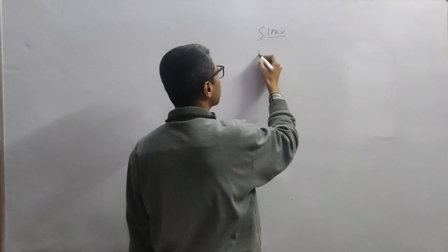This time the machine synchronizes 14 breaths of the patient into mandatory ventilation and lets the patient take 2 extra breaths. So 2 will be the extra breaths of the patient and the machine will give 14 mandatory breaths. But if it was not synchronized, it would give a total of 14 plus 16 equal to 30 breaths. So that is synchronized.